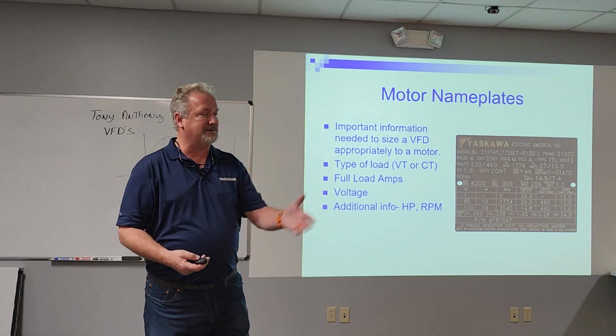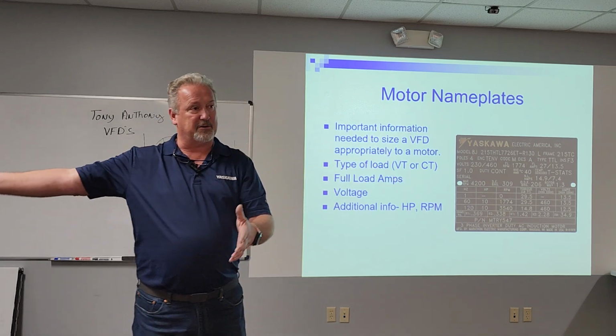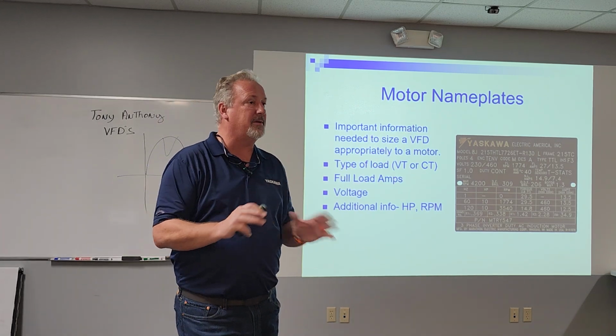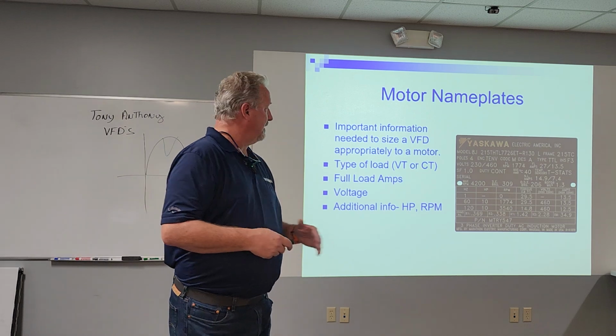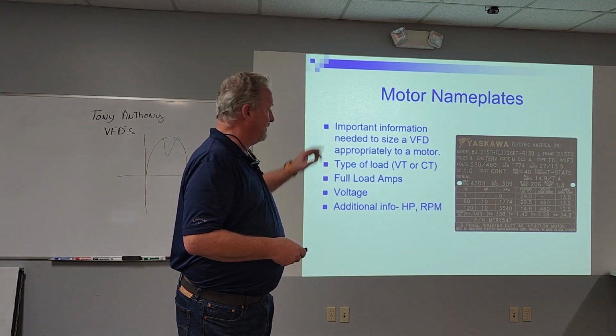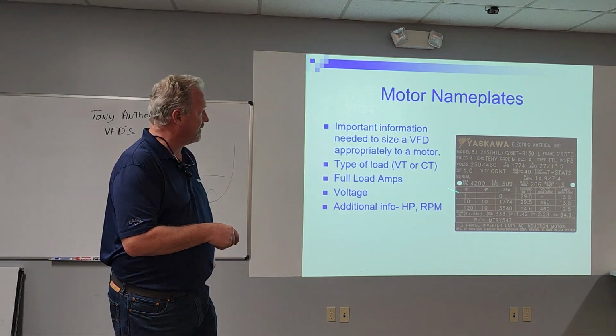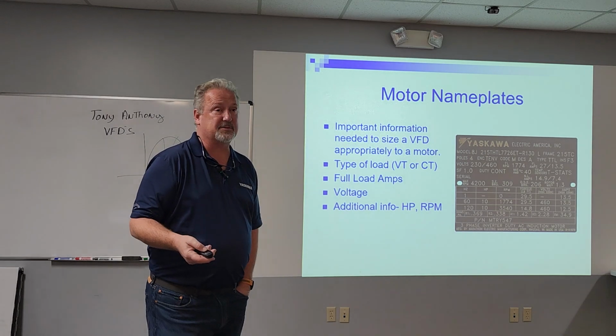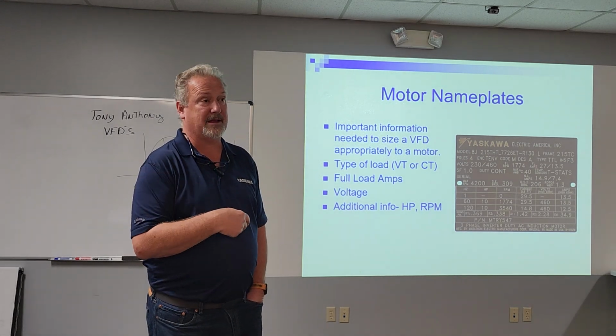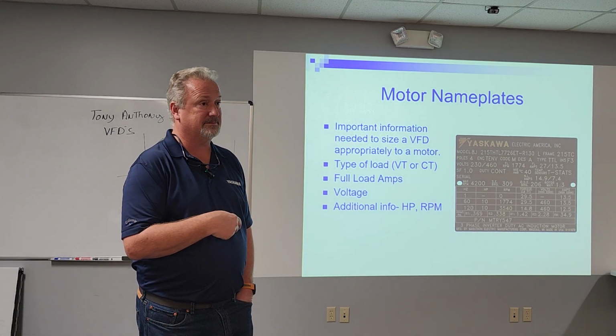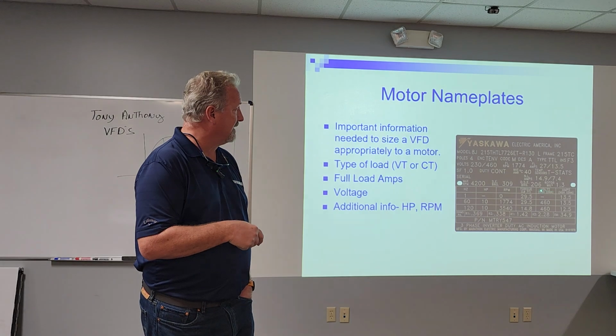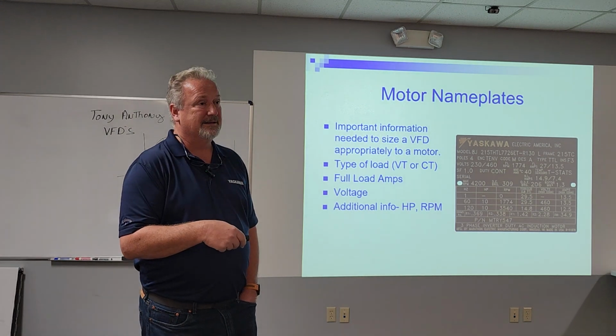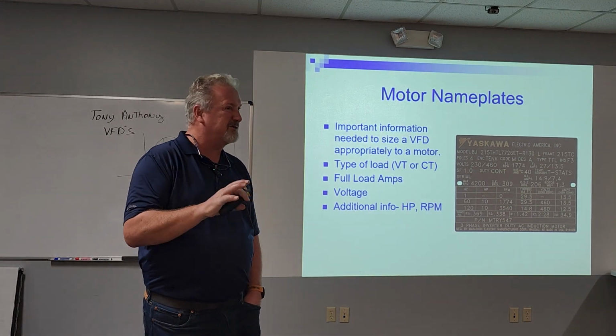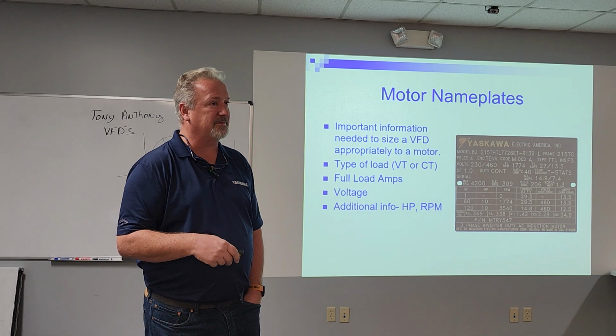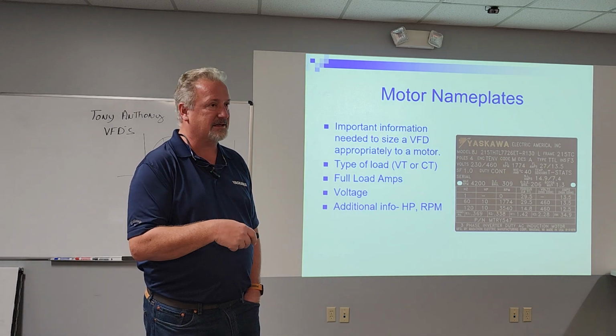But then you have to start asking things like how far away the motor is. That's the minimum we need to know: the voltage and the full load amps, the size of the motor. And all that's going to be on the motor nameplate. If a customer calls you, say, send me a picture of the motor nameplate, if they have the existing motor out there, because it also gives us the insulation class. As long as we see at least a type F insulation, we're usually okay. Not always, but usually.